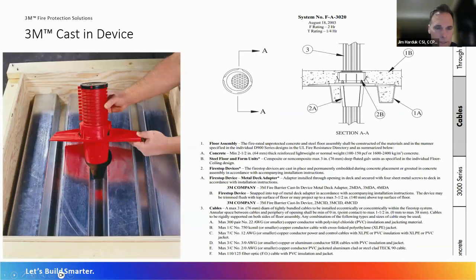And we also manufacture a plastic wing that can be attached to the cast-in device. So if you have a situation where you have a fluted metal deck, the wing is intended to span the flutes of the deck. And you'll notice on the right-hand side of the picture there's an example of our system drawing. And again, if you think back to the UL alphanumeric code, you'll notice that that begins with an F, which indicates a floor assembly. And that's exactly what you're seeing there. It's a concrete poured over a metal fluted deck with the cast-in device and a bunch of different cables being pulled through it. Next slide.